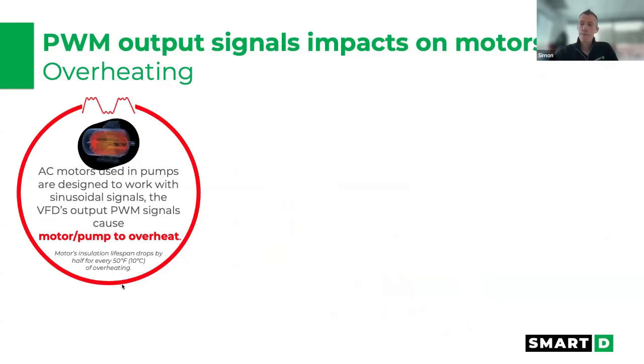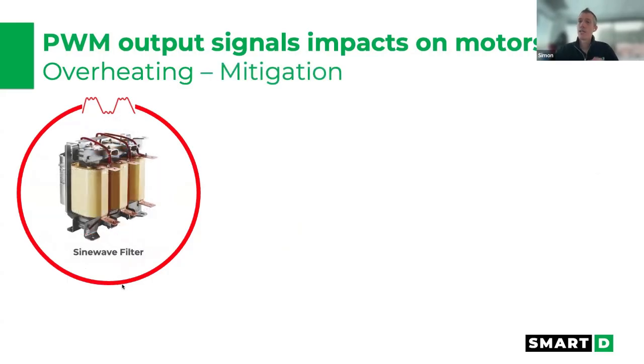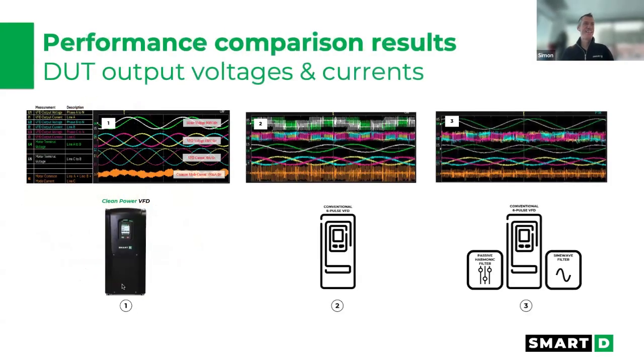And just like you have on the grid side, the main impact of harmonics on the motor side is overheating. So your motor is overheating. It needs to dissipate those harmonics in a way or another. So heat, vibration, noise. And you could mitigate that if you really wanted to remove that. You'd have to go to a sine wave filter, as we've seen in the lab results. Well, actually, we haven't seen them. We're going to see them on the next slide.